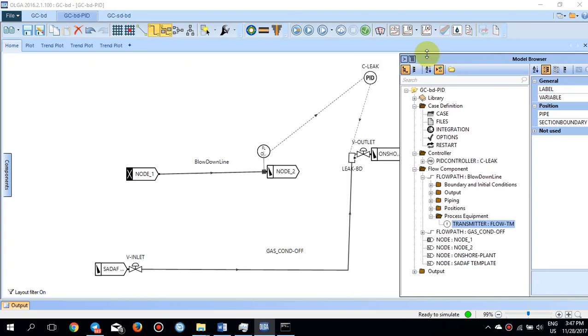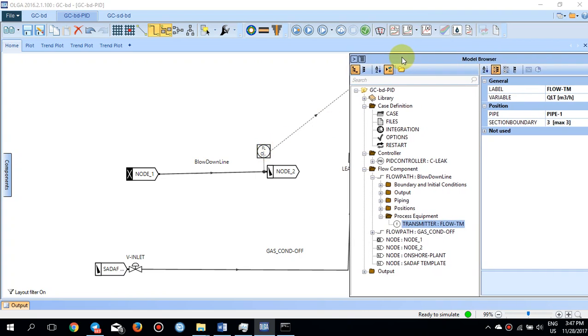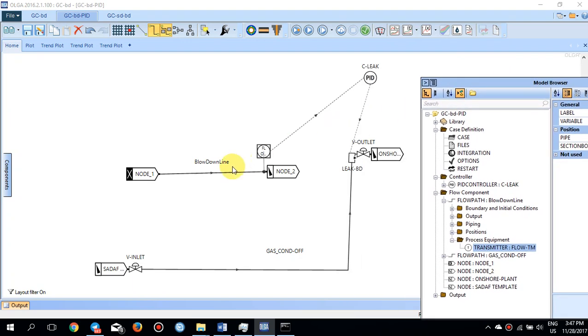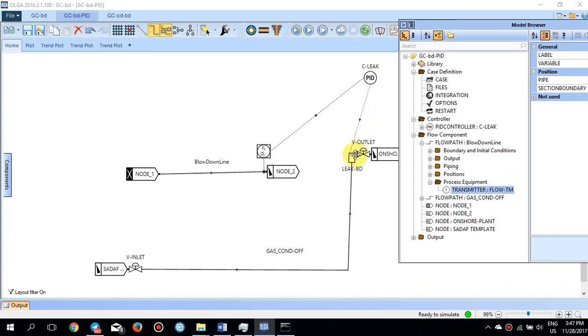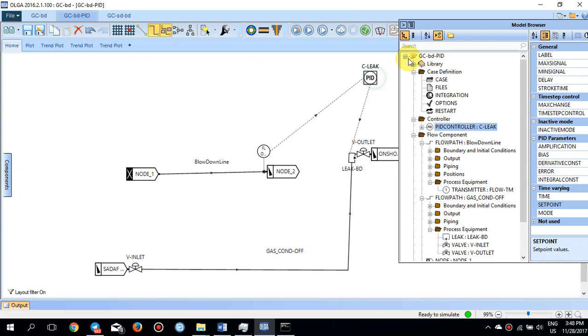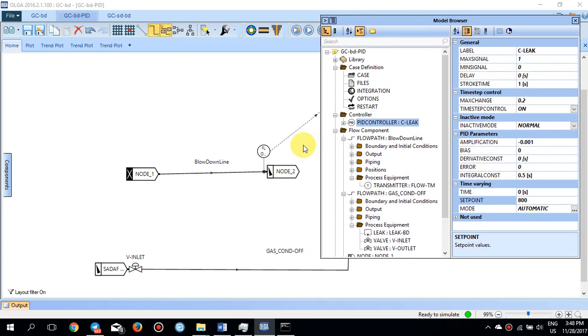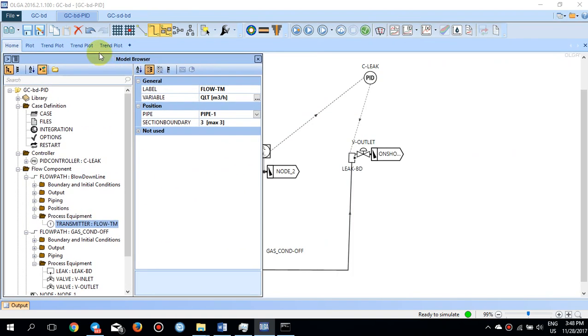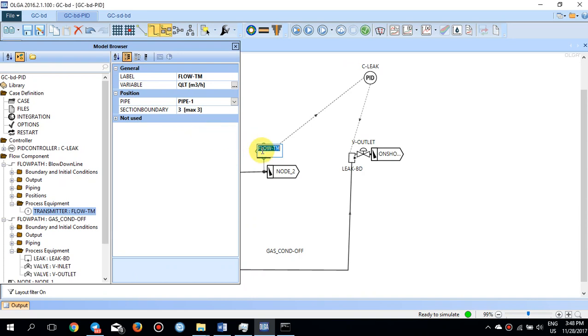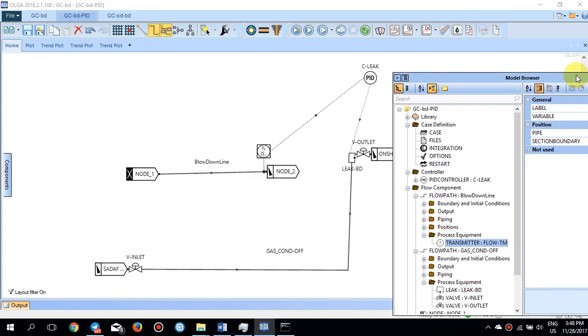I have used a PID controller instead of a manual controller. The PID controller has two connections, and there is a transmitter which measures the QLT and sends the measured value from the blowdown line to the PID controller. The PID controller continuously checks the measured value against the set point. If the set point is 800, the PID controller always checks that the transmitter's QLT does not exceed 800 cubic meters per hour — make sure the units are correct.